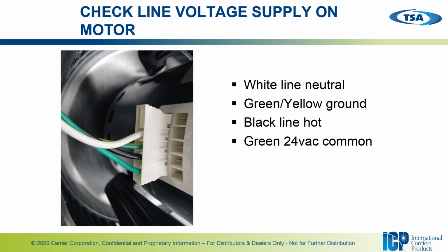Your white line is going to be your neutral. Your green with the yellow stripe is going to be a ground. Your black line is going to be hot, and your solid green is going to be your 24 volt AC common. Again, this motor has the 24 volt AC common coming into the line voltage connector.